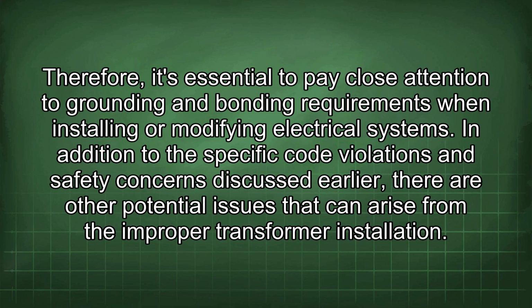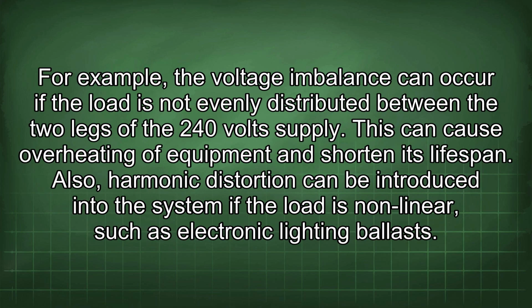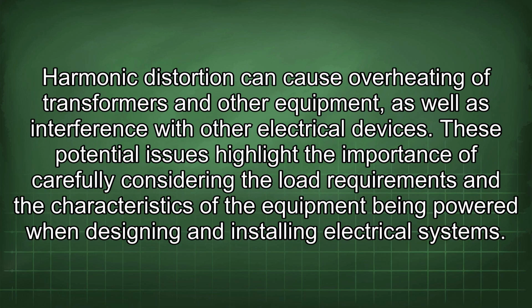In addition to the specific code violations and safety concerns discussed earlier, there are other potential issues that can arise from the improper transformer installation. For example, voltage imbalance can occur if the load is not evenly distributed between the two legs of the 240-volt supply. This can cause overheating of equipment and shorten its lifespan. Also, harmonic distortion can be introduced into the system if the load is nonlinear, such as electronic lighting ballasts. Harmonic distortion can cause overheating of transformers and other equipment, as well as interference with other electrical devices. These potential issues highlight the importance of carefully considering the load requirements and the characteristics of the equipment being powered when designing and installing electrical systems.